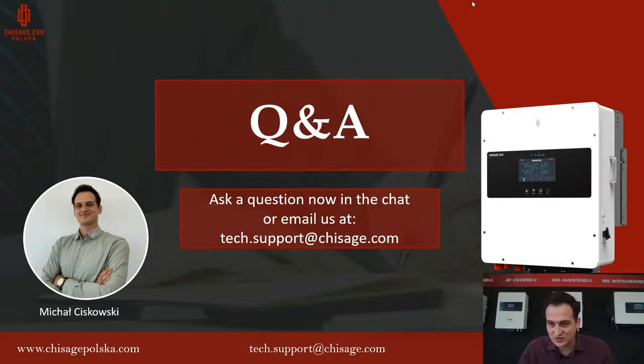What is the maximum load of the smart load on the Mars 14? Mars 14 is 14 kilowatts maximum for the smart load also. What does the number in lead battery mode mean? The number in lead battery mode is just the control number. It will change when you change the communication protocol, when you change from CAN to RS485, or you change the protocol from Pylon to Felicity. This number will change automatically, and that's only for service. We know what protocol the inverter uses, but it's just for the record, so no need to change this number.